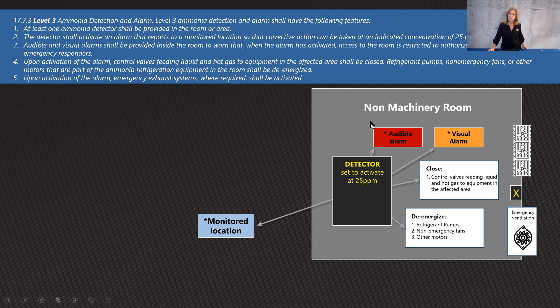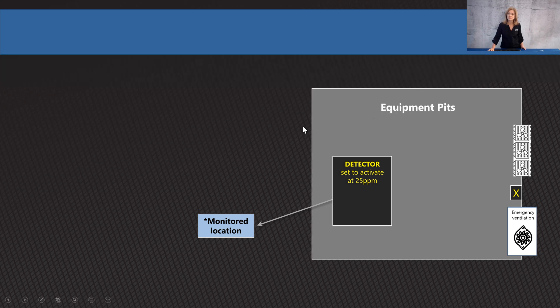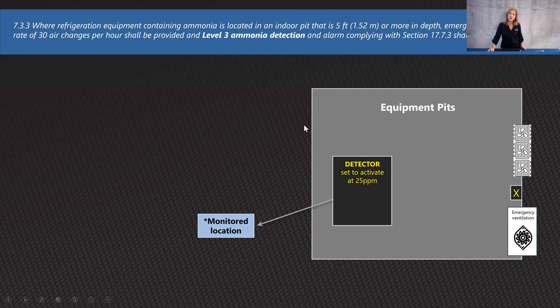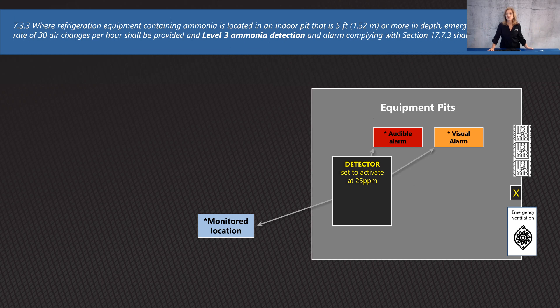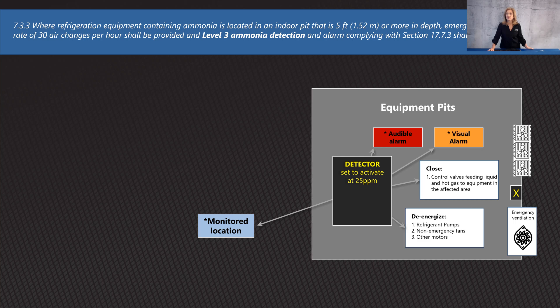For indoor equipment pits deeper than five feet, you have to have level three ammonia detection — the strictest level. This means audio/visual alarms, signal a monitored location, at least one detector, close your valves, and de-energize your pumps, non-emergency fans, and other motors.